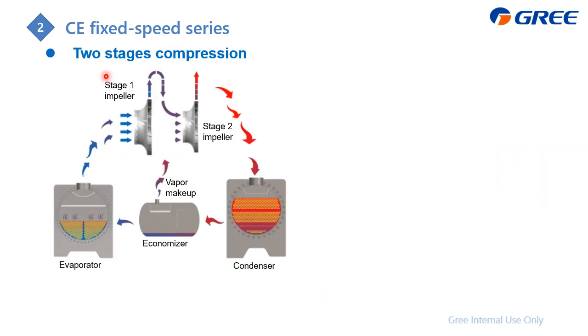And what is the two-stage compressor? Here is how it works. Here is the refrigerant out, and then the gas will flow to this condenser. Then it will become liquid, right? And the liquid will go to this economizer, and from here it will flash and become vapor, which is the gas. Then it will flow to here as the supplement for the second compression. And the majority of the refrigerant will flow to the evaporator and do cooling. After that, this one will become gas and flow to the first stage compressor. Then it compresses, and the first stage and the second stage join together for the second compression.